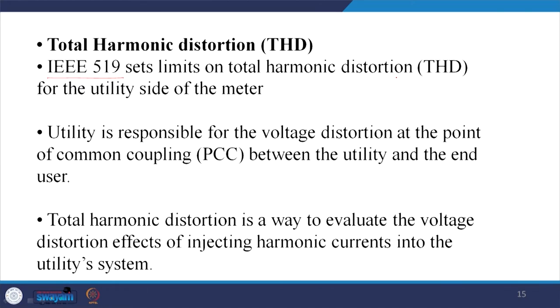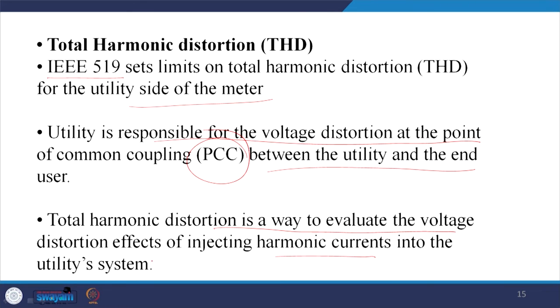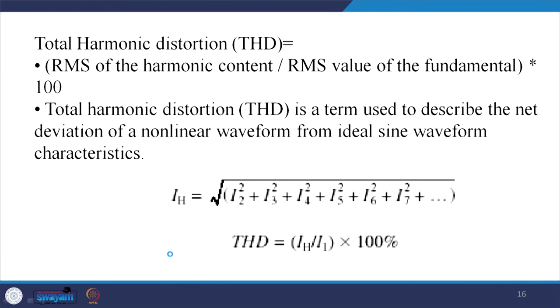According to IEEE 519, the total harmonic distortion limit on the utility side of the meter is generally restricted to 5 percent. The utility is responsible for voltage distortion at the point of common coupling — PCC — between the utility and the user. THD is a way to evaluate the voltage distortion effect of injecting harmonic current into the utility system. The cause is the non-linear load: the voltage may be sinusoidal but the current has distortion. THD of the RMS harmonic current is expressed as the RMS of harmonic components (excluding fundamental) divided by the RMS fundamental value, times 100 percent.